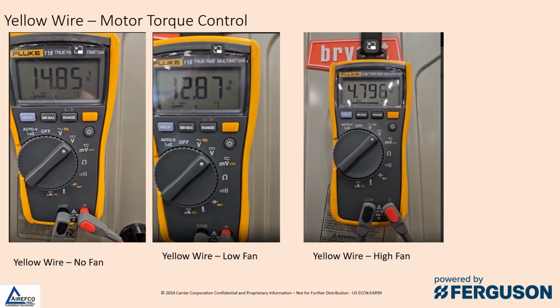So when testing the yellow wire, as we said, there's going to be 10 to 15 volts when there is no fan being called. When the furnace is running in low fan, you will see approximately 12 to 13 volts DC, and when the motor is running at high fan, you will see 4 to 5 volts DC. So you will note that the torque control will decrease the faster that the motor is operating.